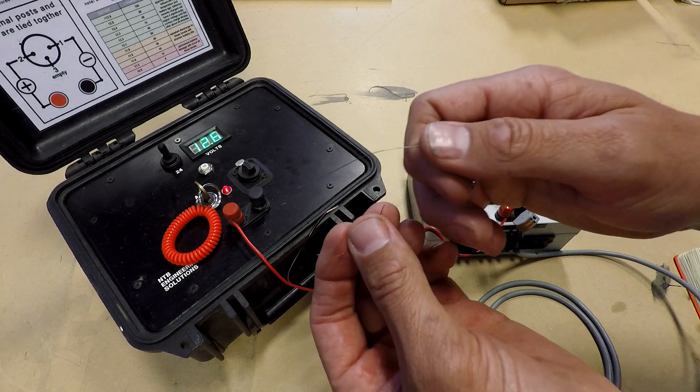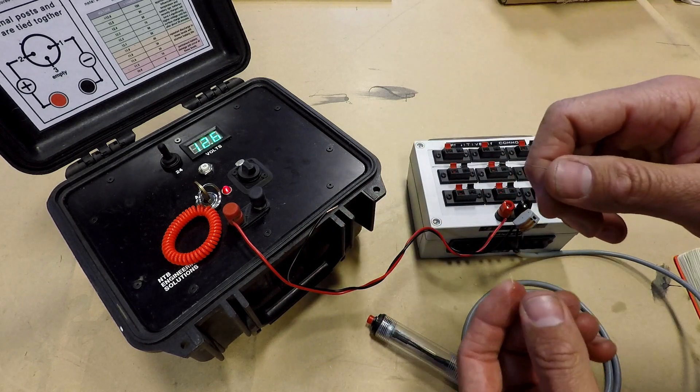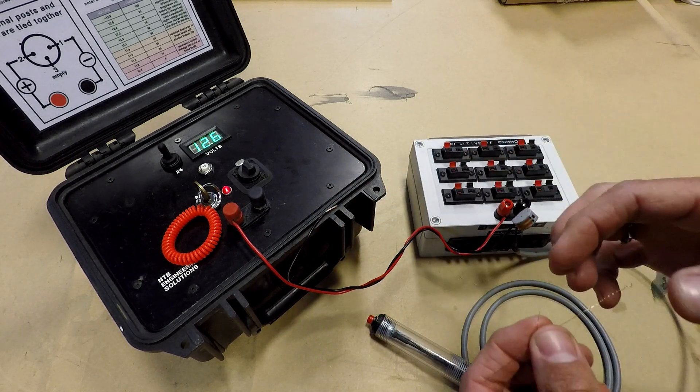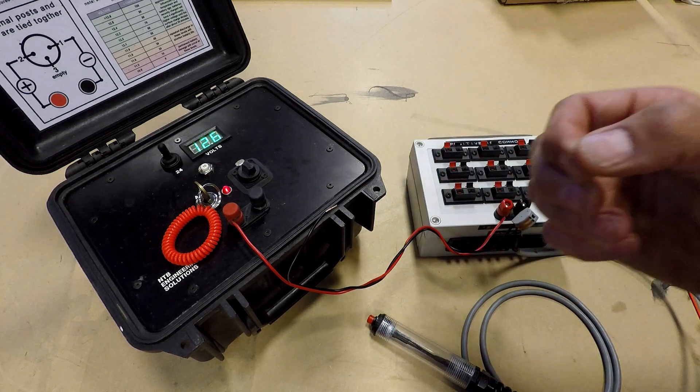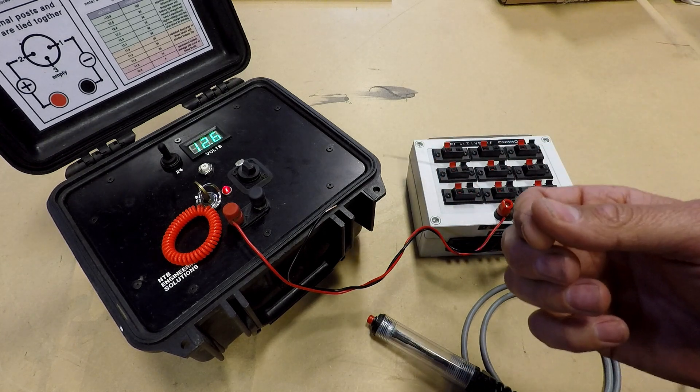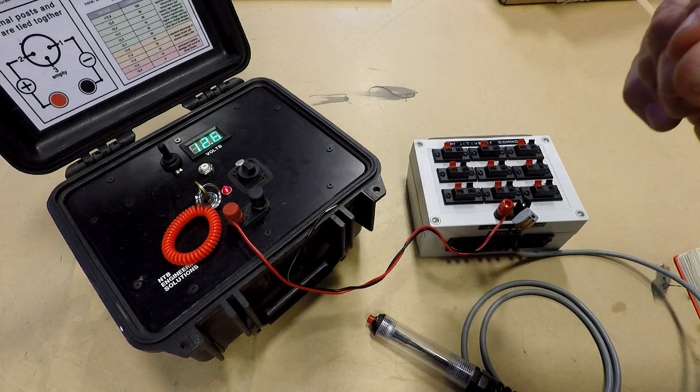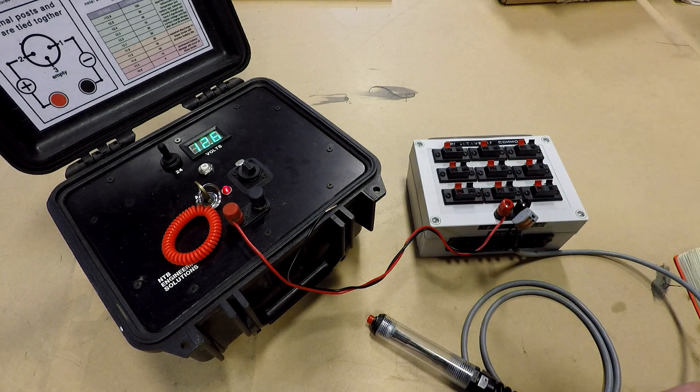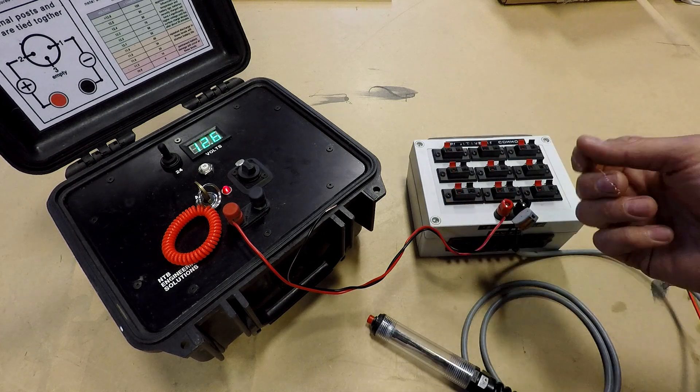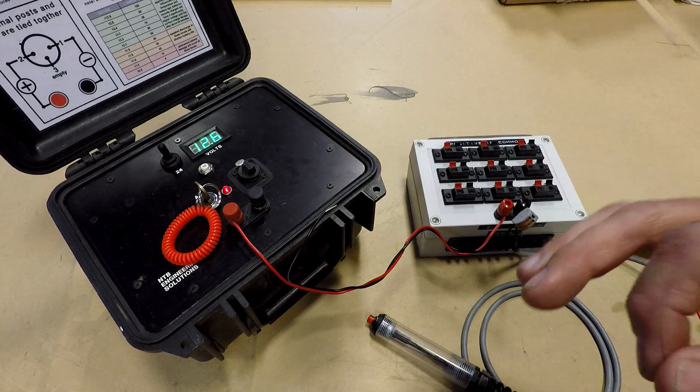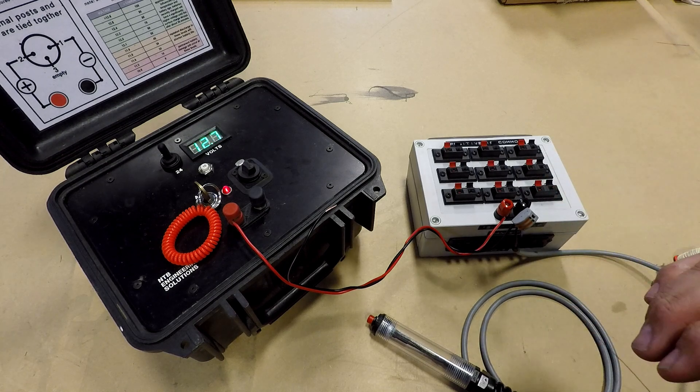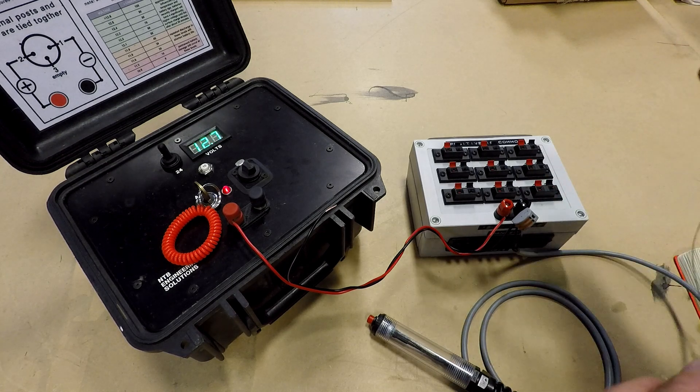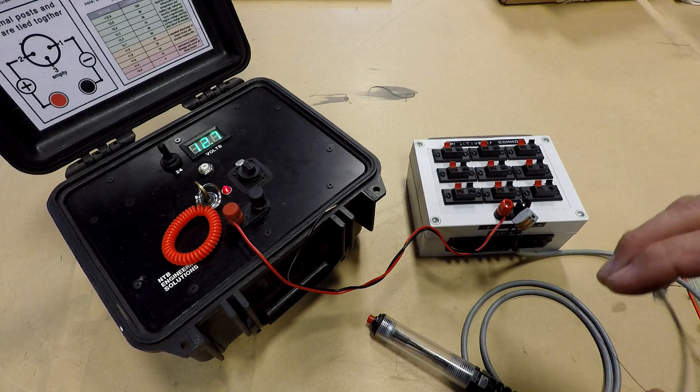So even though this tiny strand of wire passed our continuity test, under load test it failed. Now this is an extreme example. You're probably not going to have a situation like this where your entire circuit is held on by such a tiny connection, but it's an example of the sort of things you should be looking for and the sort of things you can find with a load test. Now let's set this up a little bit differently and show what happens if you've got a high resistance connection within your circuitry, which is much more likely and is less flashy.